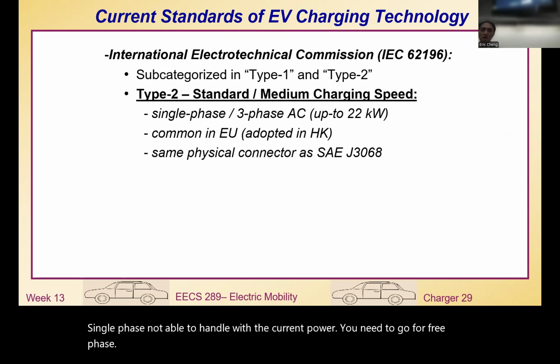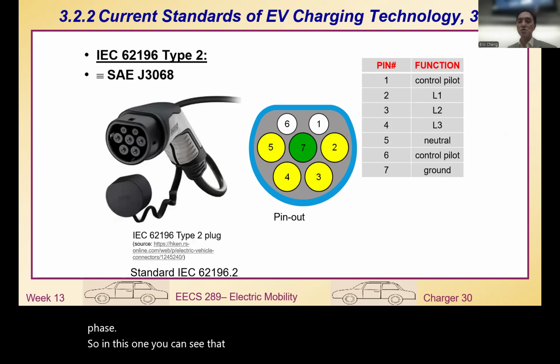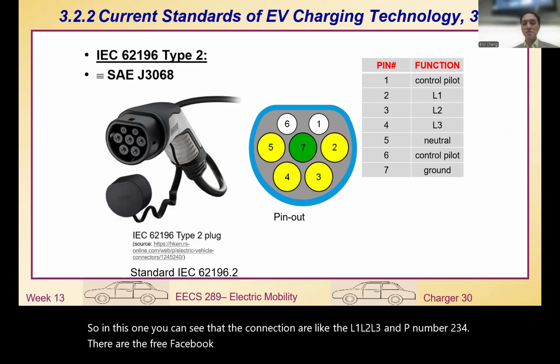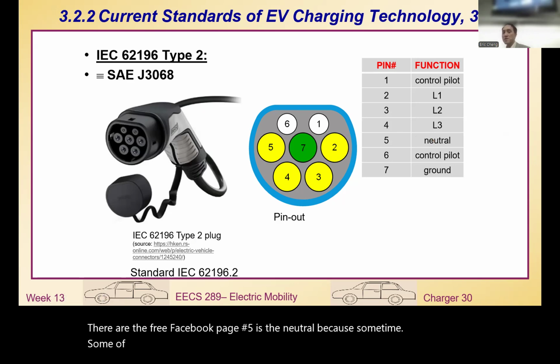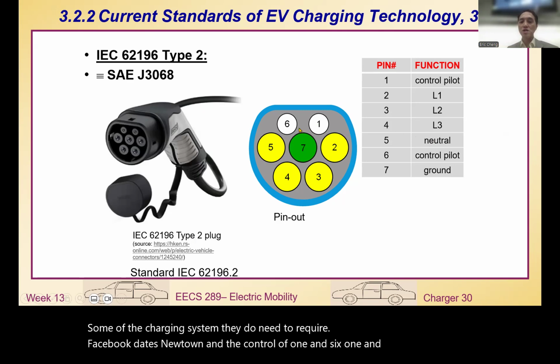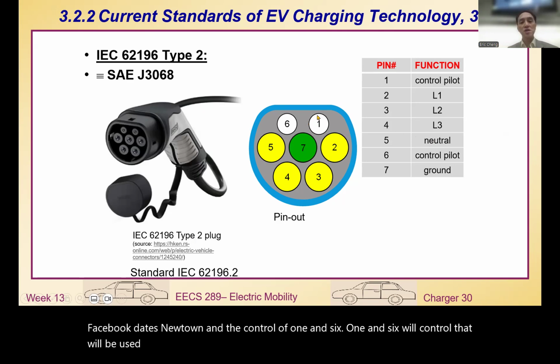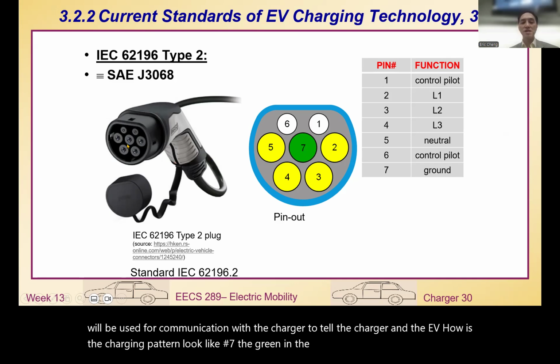In this connector, pins 2, 3, 4 are L1, L2, L3, the 3-phase line voltages. Number 5 is the neutral, because some charging systems require phase voltage with neutral. Pins 1 and 6 are for control, used for communication with the charger to establish the charging pattern. Number 7, the green one in the middle, is still the ground.